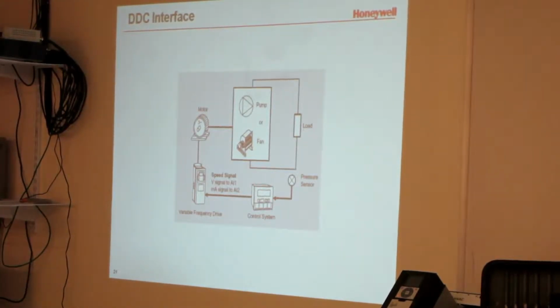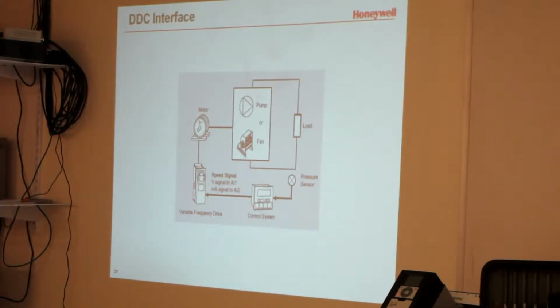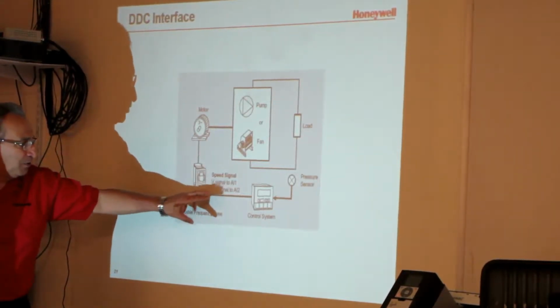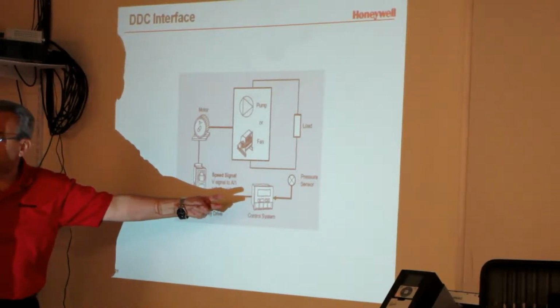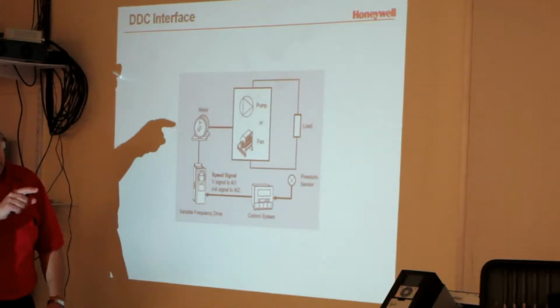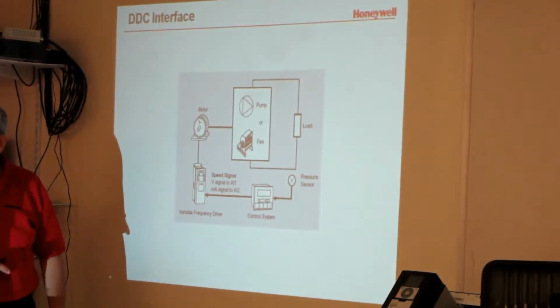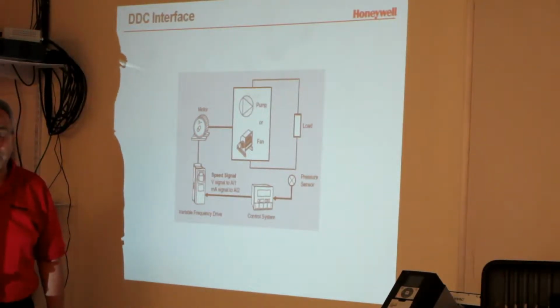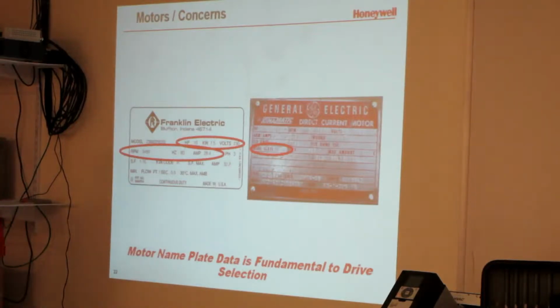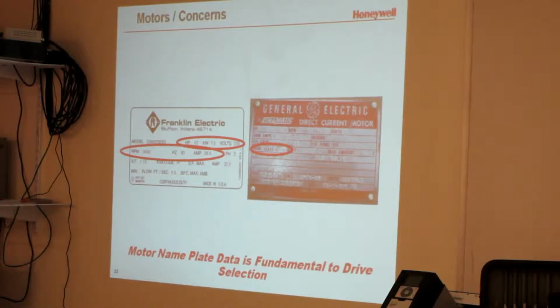XL500 router, for those of you who've seen those. This is a DDC interface. Now you can connect it to a DDC system either directly through the analog output, and you can feed back into it through the analog inputs. There is a feedback capability on these drives. I don't know any drive that doesn't have that. You could also talk on a network to them. The smart drives come with BACnet and Modbus built in. You can add a LON card if you do it LON.